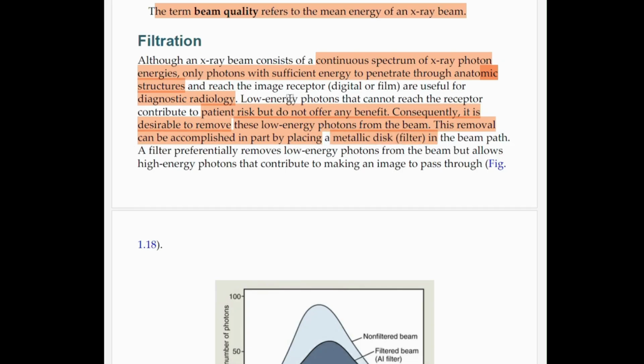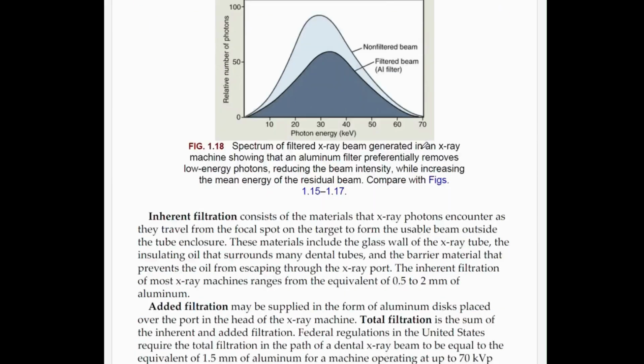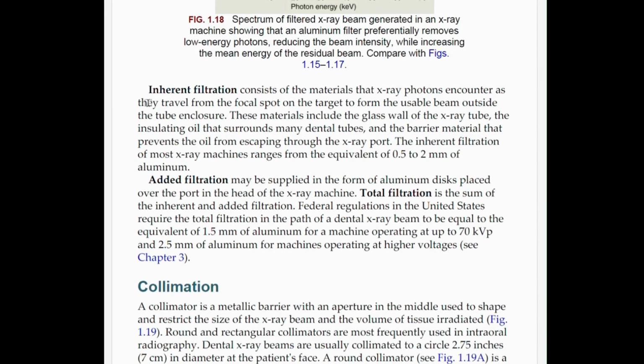So why do we need a filter? Because not all of the X-ray photon energies that are produced will penetrate through the structure and help us in radiology. There will be some that are not useful and that can be a risk to the patient. So in order to lower the risk to the patient, we will place a metallic disc, that is a filter. A filter preferentially removes low energy photons from the beam but allows high energy photons that contribute to making an image to pass through. Then there are two types of filtration: inherent filtration and added filtration.